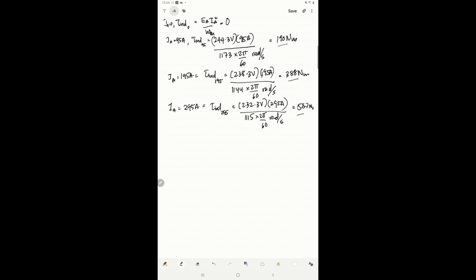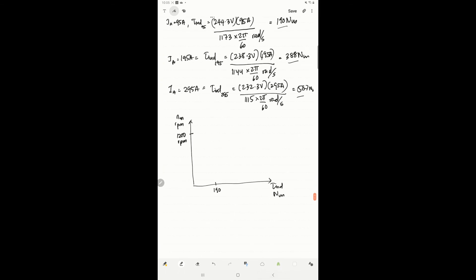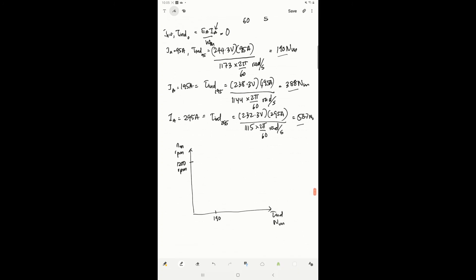Now we plot speed in rpm versus induced torque in newton-meters. At zero torque, we have 1200 rpm. At 190 newton-meters, we have 1173 rpm. At 388 newton-meters, approximately 1144 rpm, and at 587 newton-meters, approximately 1115 rpm. Connecting all these points together gives the torque-speed characteristics of this motor model.